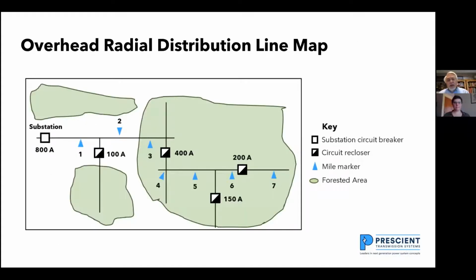So if you look, I've got a typical overhead radial distribution line here. This is a 7-mile line that's routed through forested areas, and there are reclosers along the line. So at the substation, I've got an 800 amp circuit breaker. Between miles 1 and 2, I've got a 100 amp recloser on a tap. Between miles 3 and 4, I have a 400 amp recloser in the main line. And between miles 6 and 7, I have a 200 amp recloser in the main line. So this is the basic line for a distribution line overhead that I've got today.